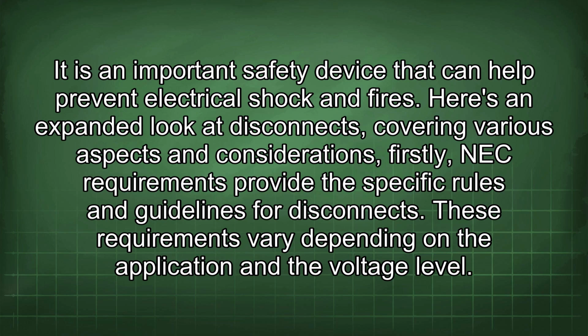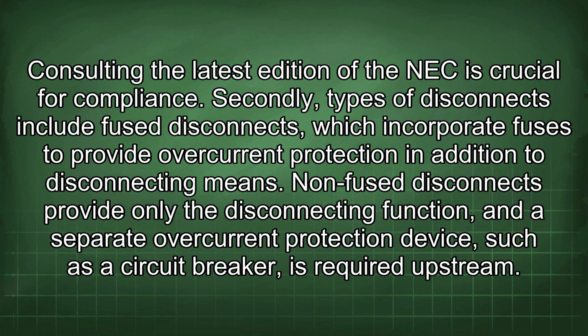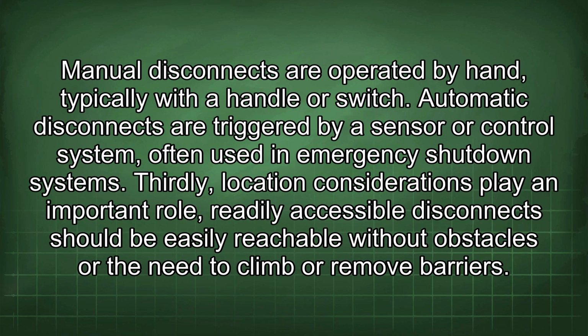Here's an expanded look at disconnects, covering various aspects and considerations. Firstly, NEC requirements provide the specific rules and guidelines for disconnects. These requirements vary depending on the application and the voltage level. Consulting the latest edition of the NEC is crucial for compliance. Secondly, types of disconnects include fuse disconnects, which incorporate fuses to provide overcurrent protection in addition to disconnecting means. Non-fuse disconnects provide only the disconnecting function, and a separate overcurrent protection device, such as a circuit breaker, is required upstream. Manual disconnects are operated by hand, typically with a handle or switch. Automatic disconnects are triggered by a sensor or control system, often used in emergency shutdown systems.